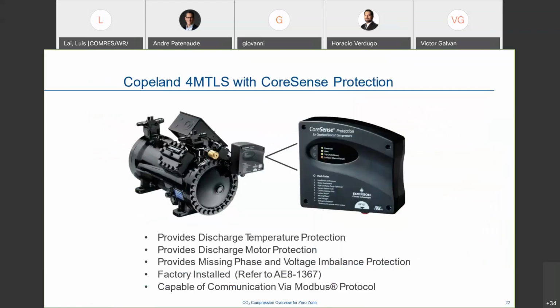CoreSense, you're familiar with CoreSense? One thing though, the models, the 40,000 BTU up to 150,000 BTU, this number one, insufficient oil pressure, is deactivated because there's no oil pump in the models from 40,000 BTU to 150. The three largest displacements do have an oil pump, so it will be enabled for the three largest displacements.